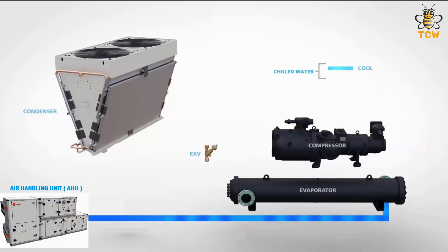When chilled water is in the evaporator, the liquid refrigerant from the expansion valve enters the evaporator. The refrigerant has a very cold temperature when it enters the evaporator. As a result of the heat absorbed from the chilled water, the temperature of the refrigerant increases to the temperature of evaporation and evaporates.